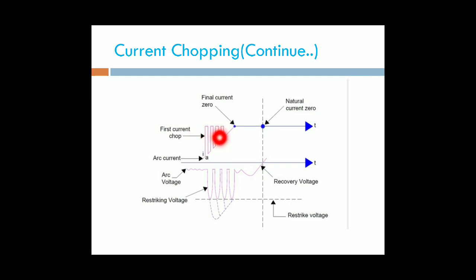In each current chopping, the magnitude of the current reduces. This is because of the damping effect of losses in the equivalent circuit, like eddy current and hysteresis losses. Due to those losses, the magnitude of the current is reduced and it may be 0 for the final chopping. This is known as current chopping.